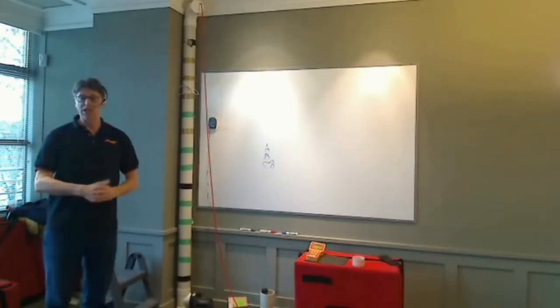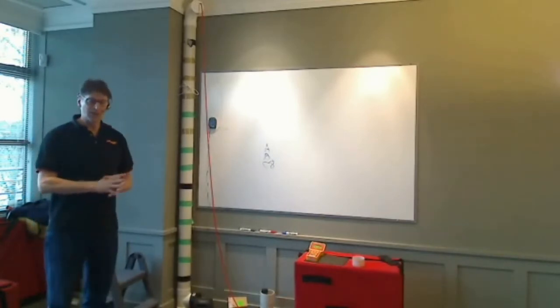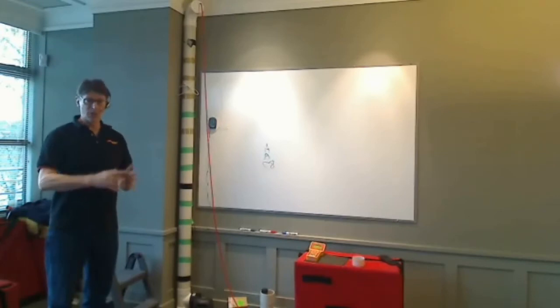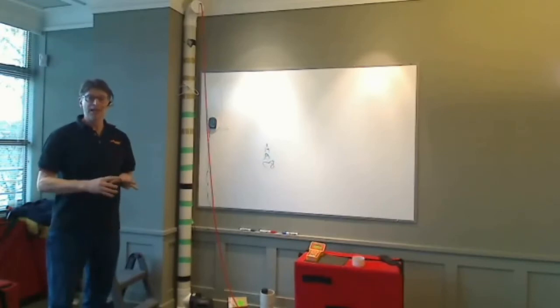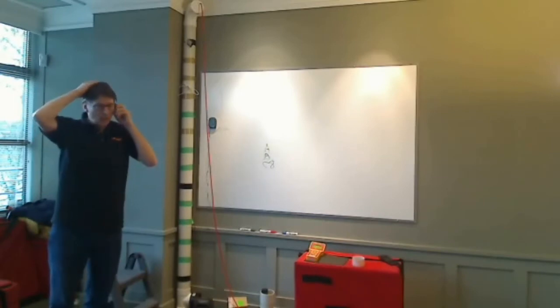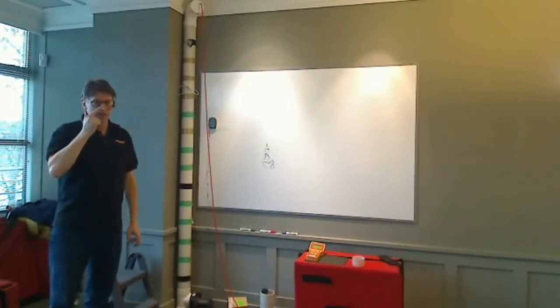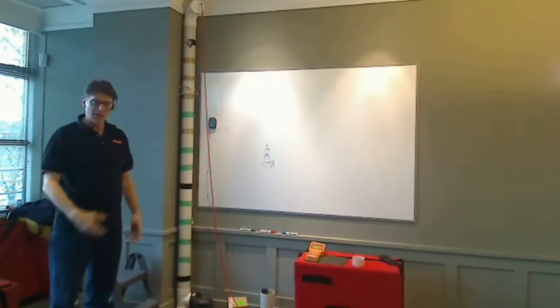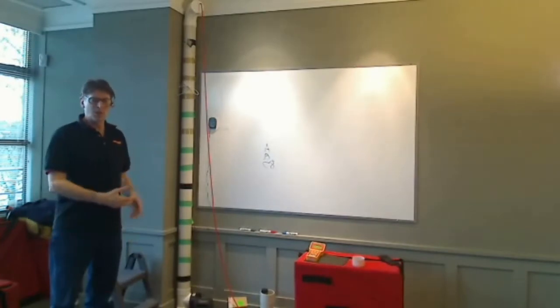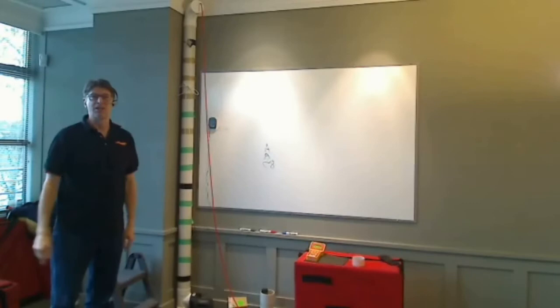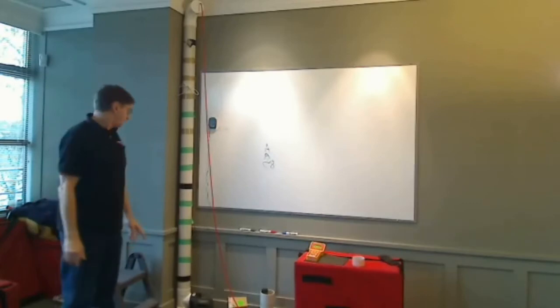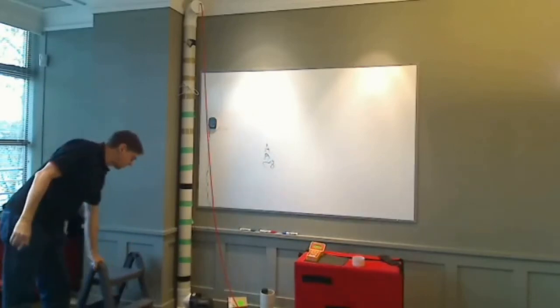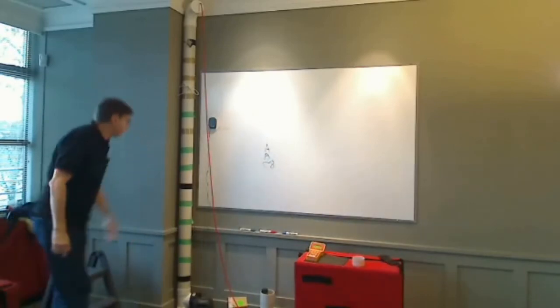This is a nice little demonstration as to how stack works. One of the things that I do sometimes, if it's in still conditions and I notice the stack on the building is really high at the top or high at the bottom, it actually tells me very inexpensively and very quickly how the building is leaking. If there's a lot of leaks at the bottom, all the pressure would be at the top and vice versa.